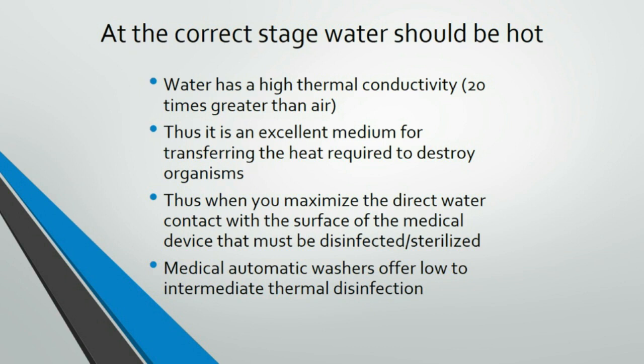When it's rinsing and it's giving that thermal disinfection, we want it to contact instruments and raise their temperature up for that thermal disinfection to happen. Thus, it is an excellent medium for transferring heat required to destroy those microorganisms. So when you maximize the direct water contact with the surface of a medical device, that's what you're getting.